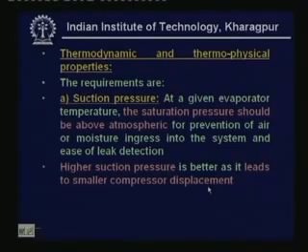That means at a given evaporator temperature the refrigerant selected should have a positive pressure, that means the operating pressure or the evaporator pressure should be above atmospheric.